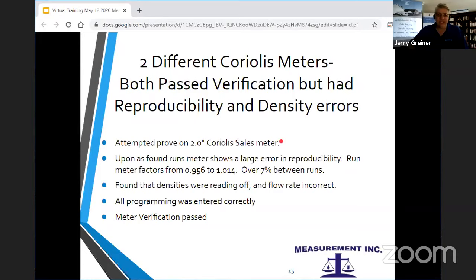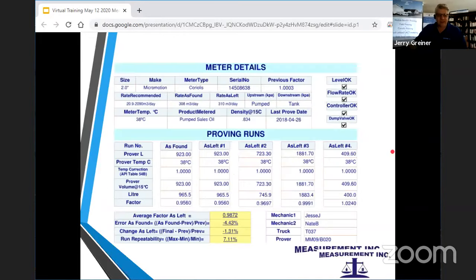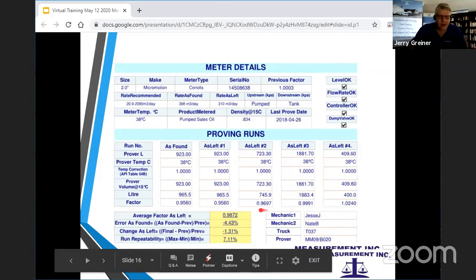And we found that the densities were reading off and the flow rate was very incorrect. Everything looked good on the programming and it passed meter verification. So here's part of our proof report. There's a whole bunch of details. The important numbers on the bottom in this yellow tell sort of the average. The average meter factor is 0.98. But the run repeatability is the one that is horrible. 7% between runs when we did this.